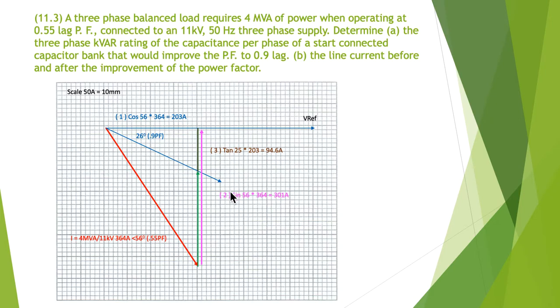Finally we can just subtract the two, so if we take our 94 and subtract it from 301, it tells us we've got 207 amps of reactive power. Remember we scaled it off and said it was around 200 amps - when we use our Pythagoras and trigonometry it actually comes out to exactly 207 amps. You can do it with both the phasor diagram and with trigonometry.